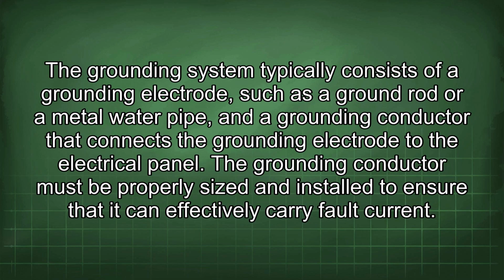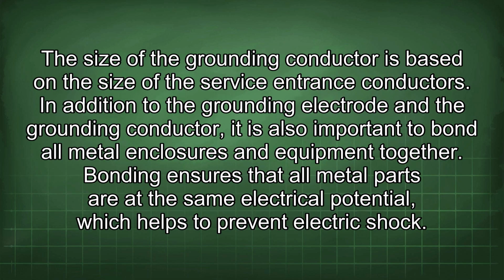The grounding system typically consists of a grounding electrode, such as a ground rod or a metal water pipe, and a grounding conductor that connects the grounding electrode to the electrical panel. The grounding conductor must be properly sized and installed to ensure that it can effectively carry fault current. The size of the grounding conductor is based on the size of the service entrance conductors.